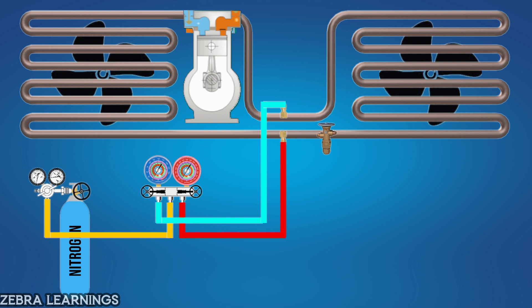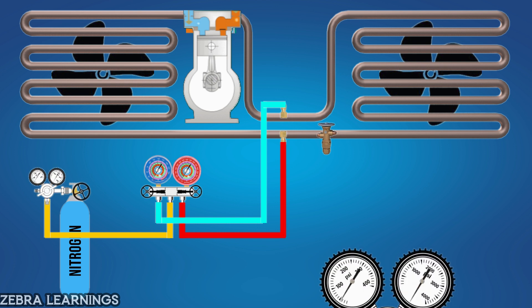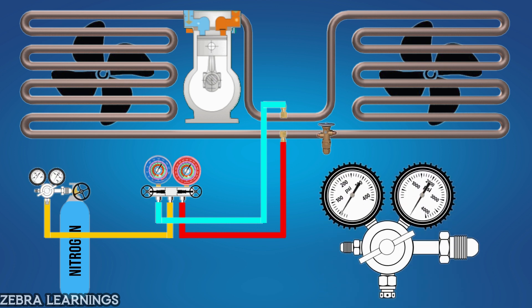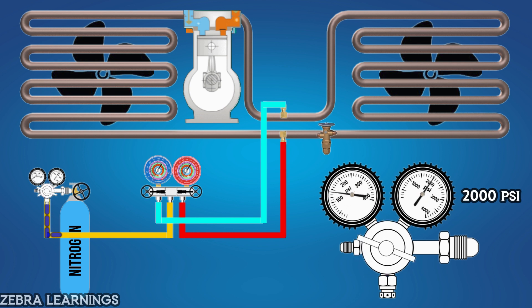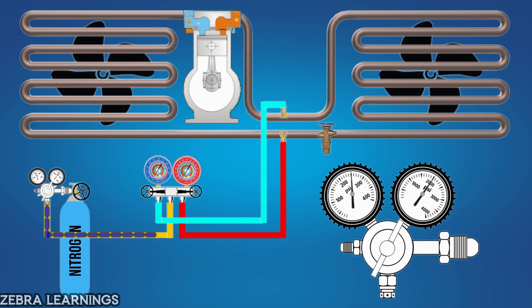Now open the cylinder. When you open it, you can check the pressure in the cylinder using the first gauge. Then adjust the handle in the middle of the regulator clockwise to set the pressure that will be applied to the AC unit. In this case, we will set the pressure to 250 psi.